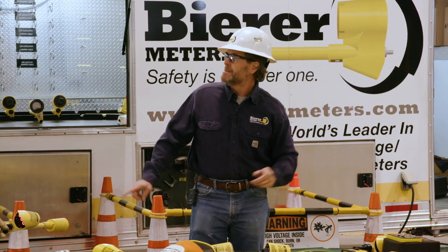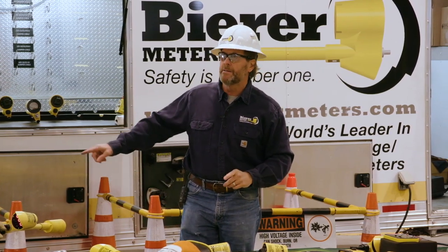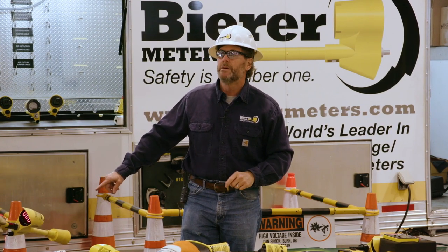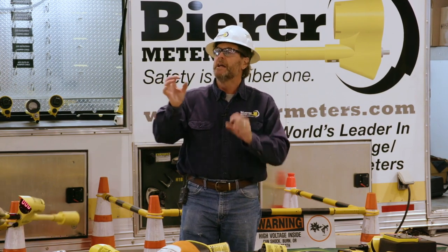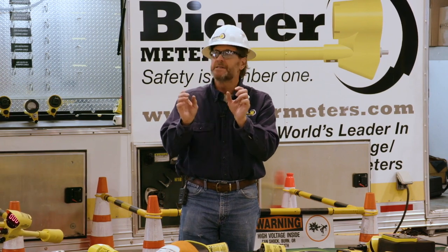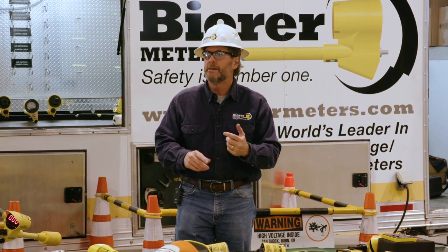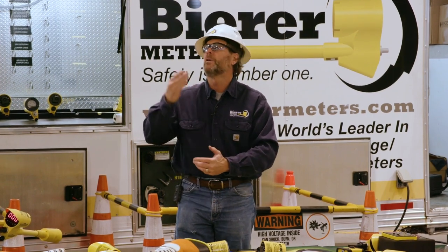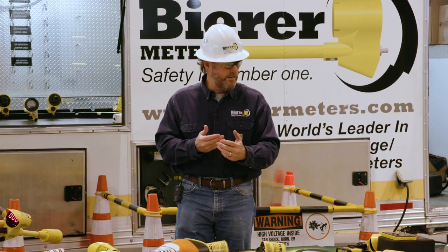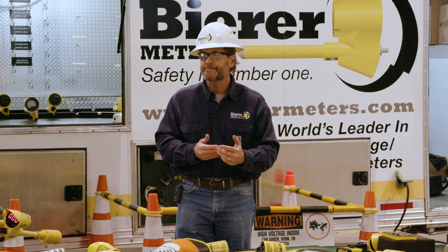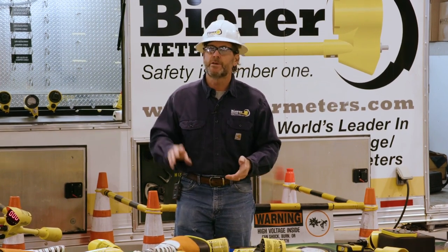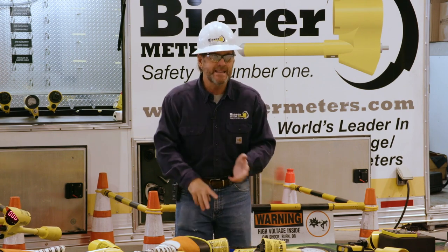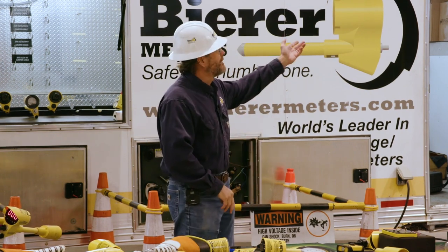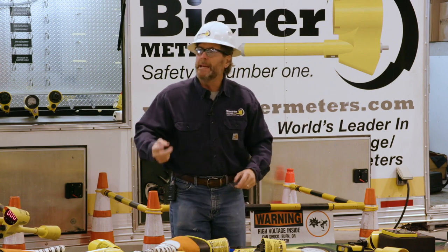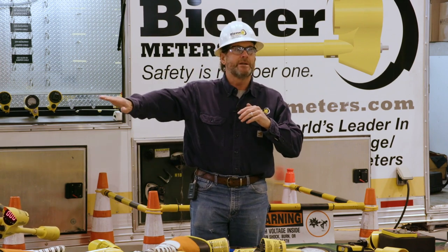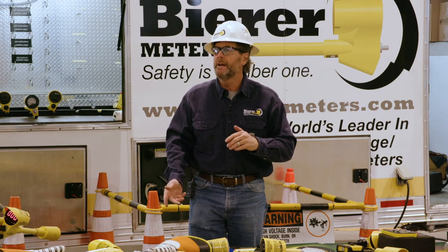And if it's the same phase, Mr. Robbie's going to see a white light on the meter, the PD800W. He's going to see a white light, and he's going to see the numbers, the LED display, saying close to zero. It could be a little under, it could be a little over, depending on leading and lagging power factors, but it's going to be close. So he'll get two confirmations that it's the same phase. If A is our reference, that's our zero, that means B is the next phase out of sequence. So B will be a blue light and 120 degrees.